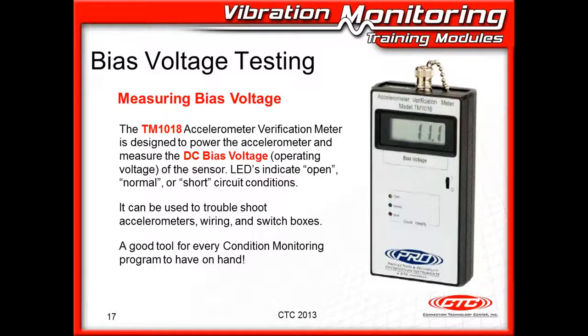You can start right out if you have a switch box and connect this to the switch box. Now you're checking the switch box, the cable, and the accelerometer. If you find a problem, disconnect the cable and just go with the cable and the sensor. If you're still seeing issues, disconnect the sensor and just test the sensor. So a very good basic troubleshooting tool for electrical circuits and connectivity and just making sure you've got the power in the right place at the right time.